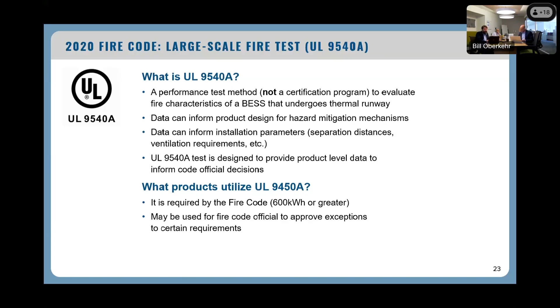This is why we're supposed to remember the building blocks. The UL 9540A test happens at different levels of the system: the cell level, the module level, the unit level, and the installation level. The first three - cell, module, and unit - aren't allowed to have any fire suppression or other measures built in to alter the results. These are just raw results of how the battery reacts when thermal runaway is induced. The installation level test, if necessary or required by the AHJ, is where we can build in fire suppression systems, explosion control, and see how the system reacts with those fail-safes in place.